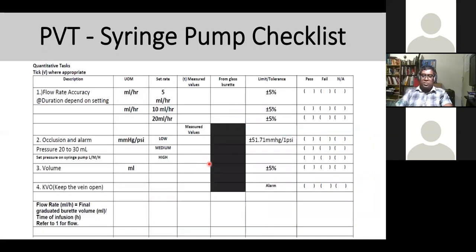The checklist should look like this. So for flow, you can do 5, 10, and 20. This is a basic checklist for syringe pump. And these are the tolerance of 5% plus minus. And you can do the occlusion alarm. You got mmHg and PSI. And the minimum pressure should be somewhere 51.7 mmHg or 1 PSI. That's the minimum. And you can see low, medium, and high. That indicates the pressure line setting. So normally you have to refer to the user manual. On the user manual, it will mention the low, medium, and high setting on the syringe pump itself.